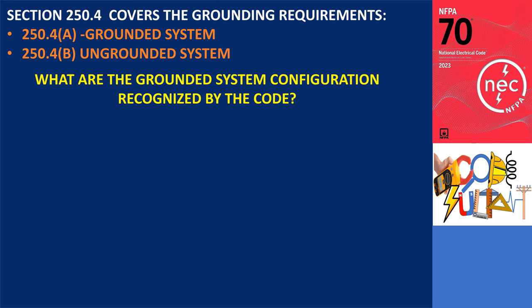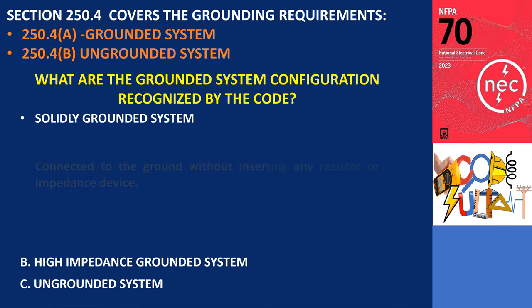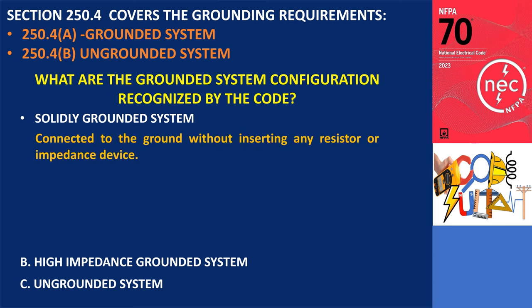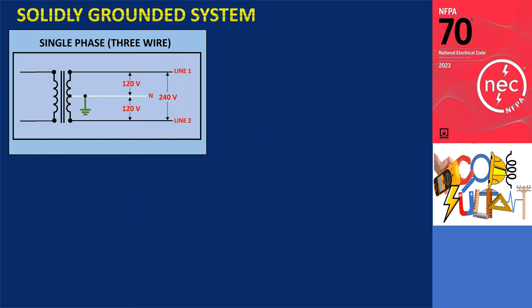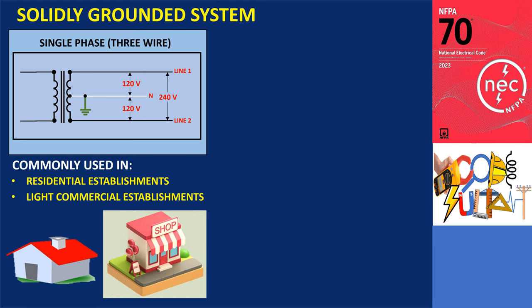This section covers the grounding requirements for grounded systems under Section 250.4A and ungrounded systems under Section 250.4B. There are different grounding systems recognized by the Code: the solidly grounded system and the ungrounded system. Solidly grounded is defined by the Code as connected to the ground without inserting any resistor or impedance device.